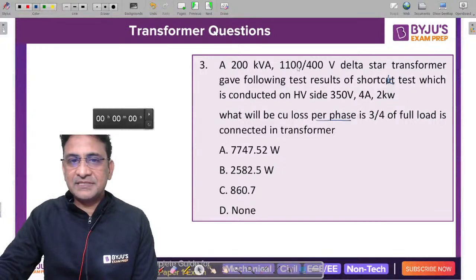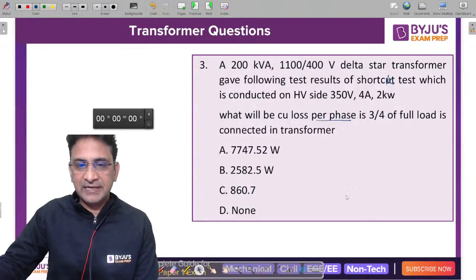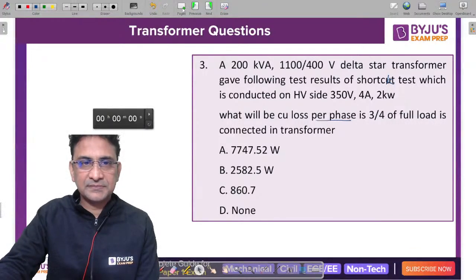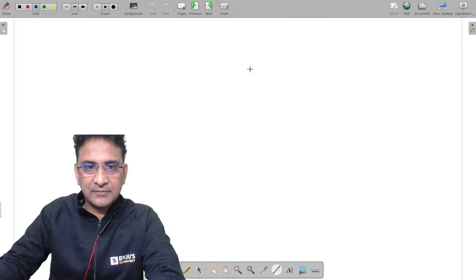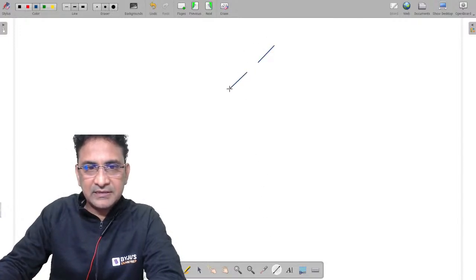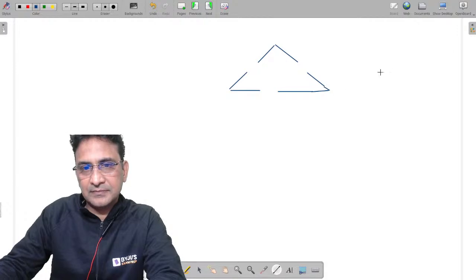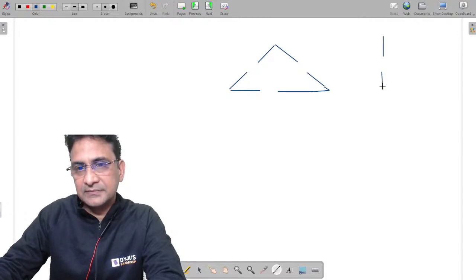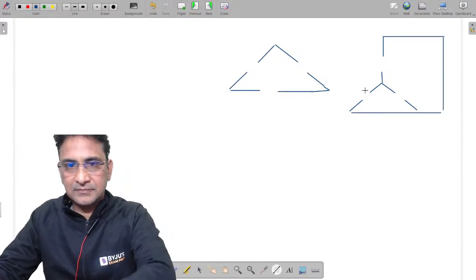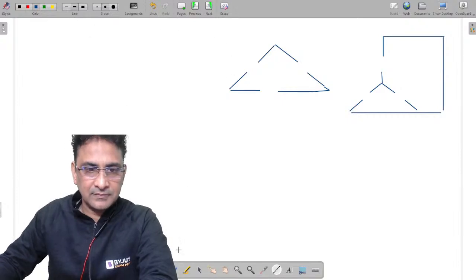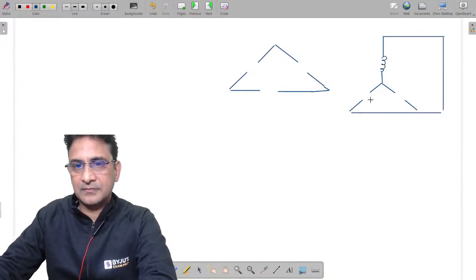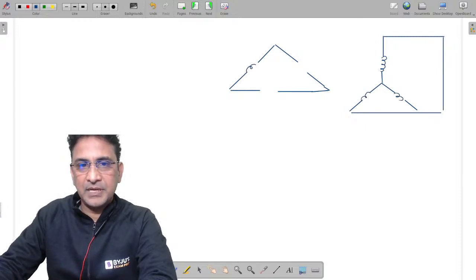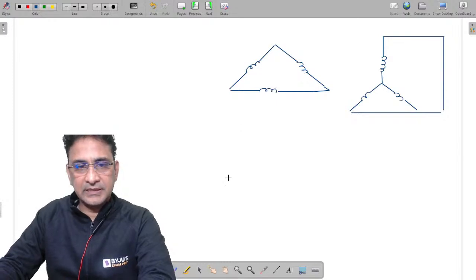It is a delta star. That means three-phase transformer. Primary winding, high voltage side winding, is connected in delta, and secondary winding is connected in star. So see, this is the primary winding which is connected in delta. Secondary winding is connected in star. Secondary side is short circuited. Primary winding is delta connected.